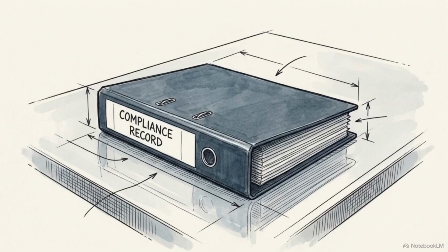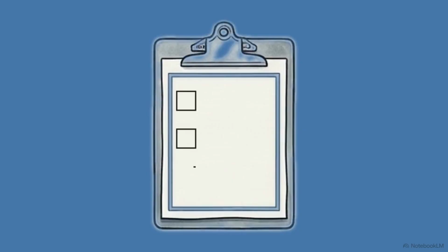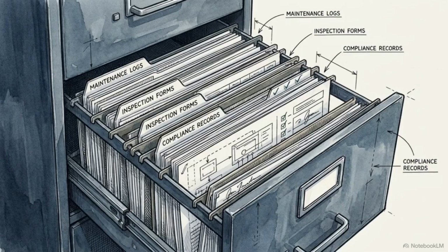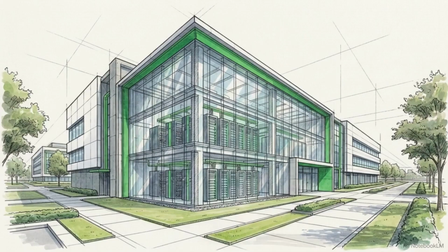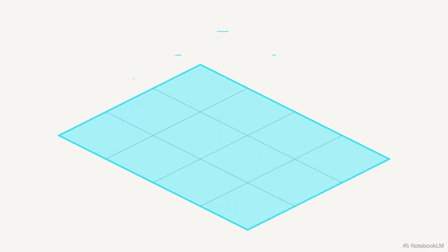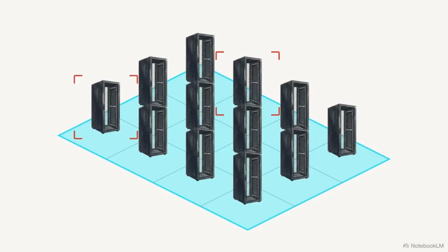Surviving these audits requires documented, reasonable care. This means maintaining logs of battery replacements and load testing to prove you protected the data. Documented proof of maintenance serves as a financial safeguard, ensuring the organization can demonstrate compliance during a post-event audit. Addressing the liability tail doesn't require an immediate capital overhaul. It begins with mapping the hidden risks inside your current environment.